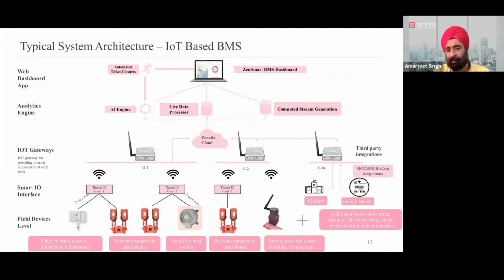So how do these things come together? This is a typical system architecture, right? You would install some of these battery powered sensors. It could be vibration sensors, temperature, humidity sensors, pressure sensors, etc. They talk wirelessly to the gateway. Then you would install those wireless IO cards on your field devices. It could be a pump, it could be a sensing device. These get connected via this control card, and you can start doing both sensing and control via this control card, and the control card also wirelessly gets connected to the gateway.